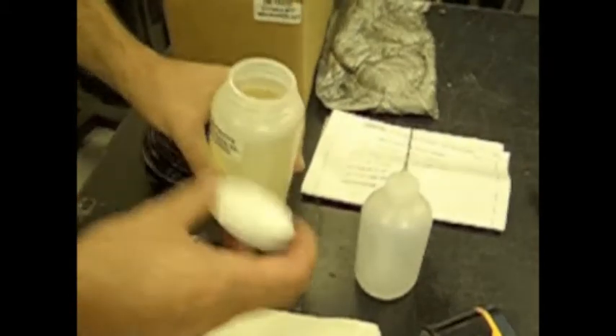Unless a hydraulic line or fitting has been damaged, you will not need the extra line and compression fittings and ferrules. The first step is to fill the smaller bottle about half full with hydraulic fluid and secure the needle tip.